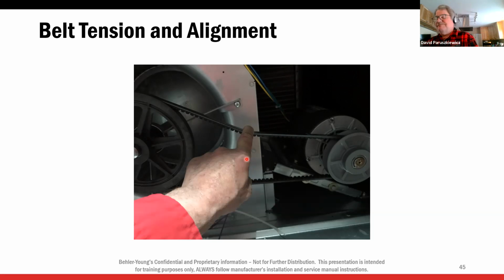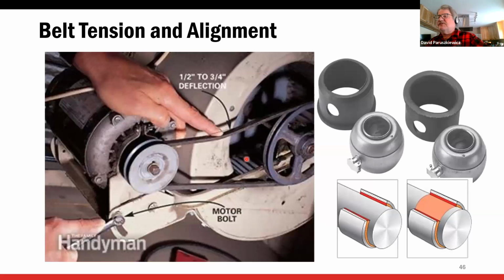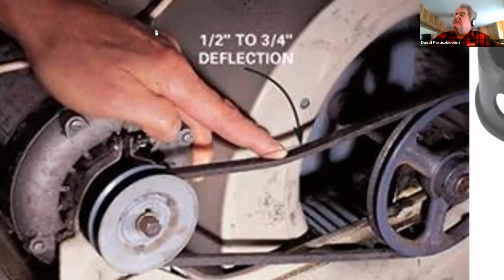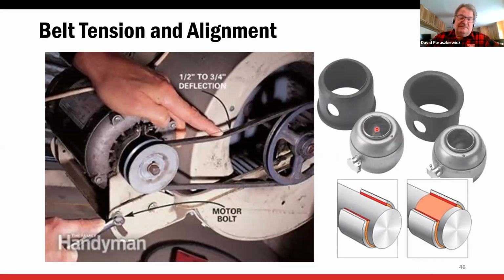Now, this belt tension is one that comes up a lot, and I want to talk about it for a second. I remember this from when I went to community college 150 years ago. We always talked about the deflection on the belt: 1/2 inch, 3/4 of an inch, 1 inch. Everybody remember that? That was for sleeve bearings, a brass sleeve that the shaft runs in. This is not what we're dealing with. So do not look for that 1/2 inch or 3/4 or, worse, 1 inch of deflection in that belt. That belt is way too loose. It's going to slip. We're never going to get full speed.